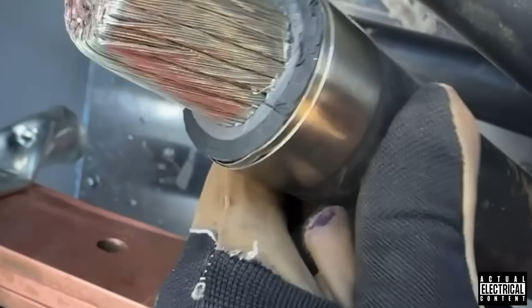And then here, I've got to get this plastic bedding out and make sure it's out all the way around, otherwise I'll be crimping onto an insulator. So now I'm inspecting it, see there's a bit of plastic left, that would be no good. That needs to come off all the way around. I left it on purpose, to be honest, but there, look, I need to take that bit of plastic off, because that would be resistive, very resistive.